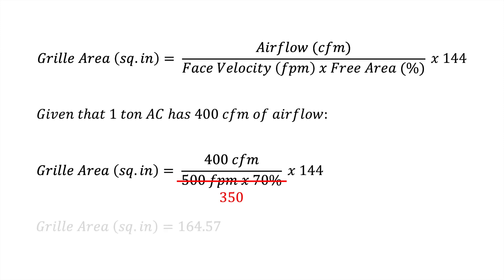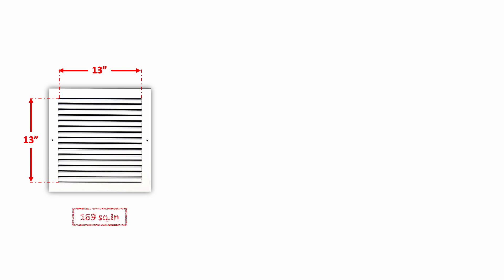The grill size is 164.57 square inches. We can use any grill size that has more than 164.57 square inches. For instance, we can use a 13 inches by 13 inches grill, measured on the inner side of the grill. The grill area is 169 square inches.